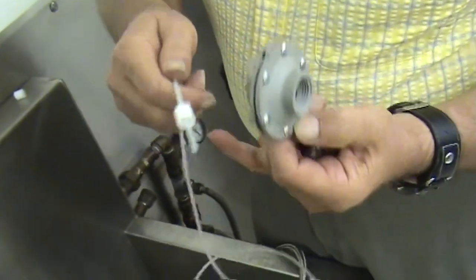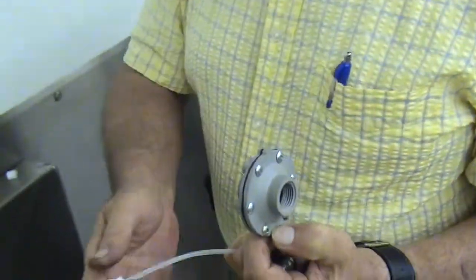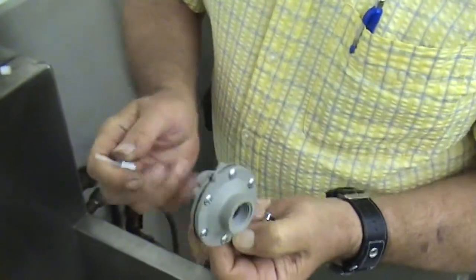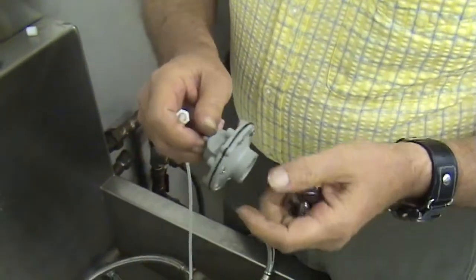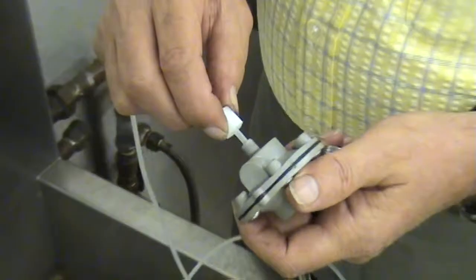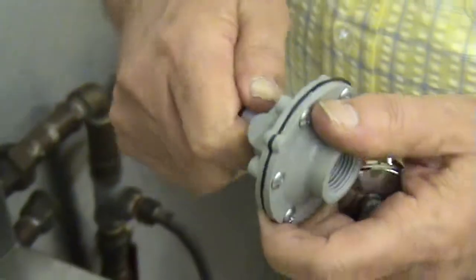It comes with a little white compression nut that attaches the small air tube to it. So you get the new pod. Make sure your tubing bottoms out the fittings. Slide up your nut before you make your connection. That's the proper way to make this compression joint.